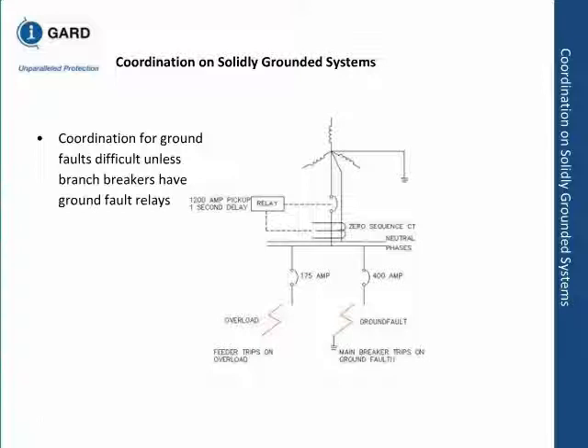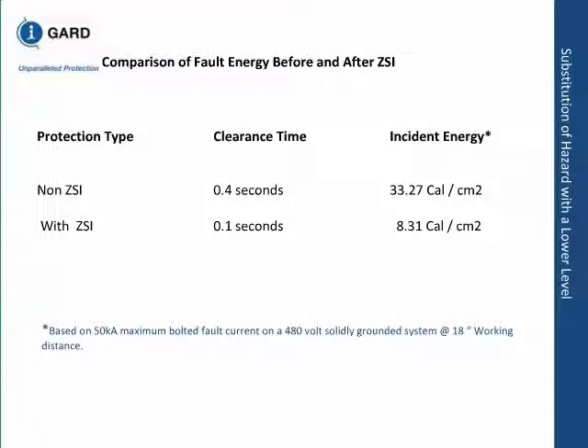If you don't have zone selective interlocking, clearing time with non-selective interlocking, which is going to be short time, is about 0.4 seconds, and you can see you get about 33 calories incident energy. If you have zone selective interlocking, you have cut down the time to 1/10 of a second. Now you have 8.31. People who are math experts can probably see the relationship. When the time went down by 4, so did the energy, because incident energy is proportional to I squared T, the square of the current times the time it takes to clear. And this is based on 50 kA fault current, same thing as we had before.